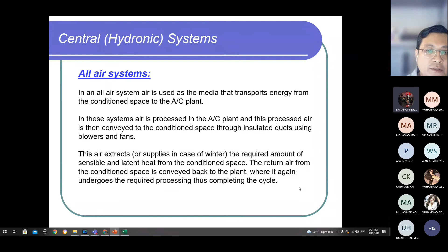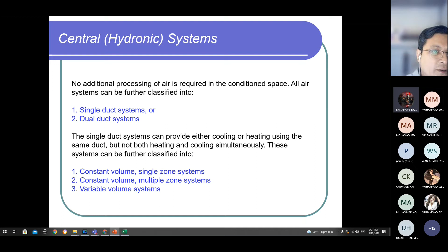So actually, for the air supplying system, a hydronic system will be implemented by two duct systems. The first is the single duct system, and the second is the dual duct system. A single duct system will provide one condition of air for a certain duct. For example, for hot conditions, it will supply hot air. If we implement a single duct for a cold system, only cold air will be provided in the single duct system.